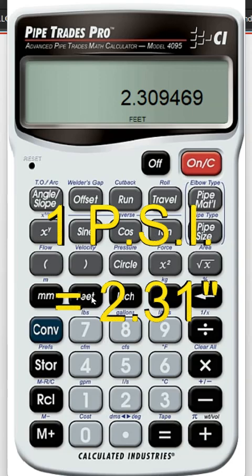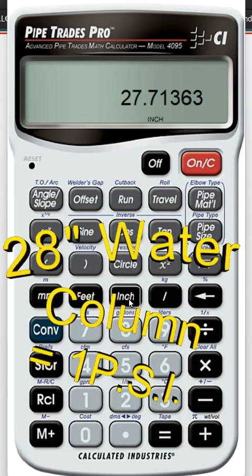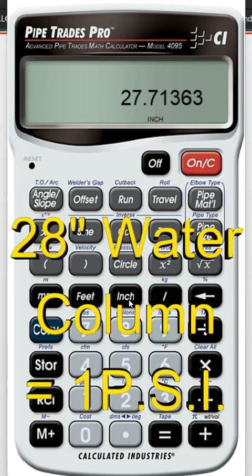So if we take that feet and we convert that to inches, we get 28 linear inches. That's where we get 28 inches of water column equals 1 psi.